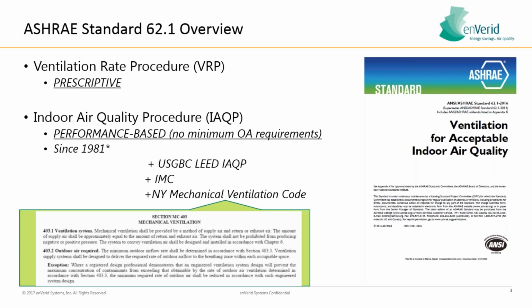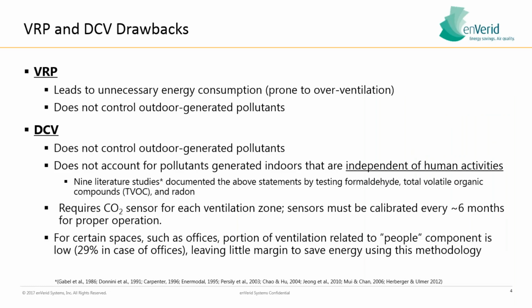So the only outside air requirement is the outside air that you need to pressurize the building to overcome toilet exhaust and other things like that. And that enables you to see massive energy savings because you're not having to condition outside air that's under non-ideal humidity or temperature conditions. So let's talk about ventilation rate procedure and demand control ventilation, which many folks are currently using today.